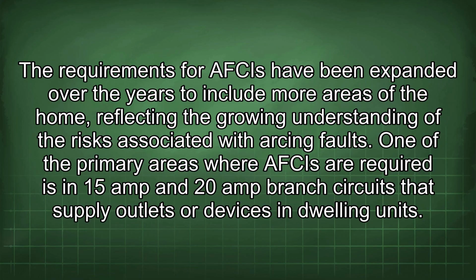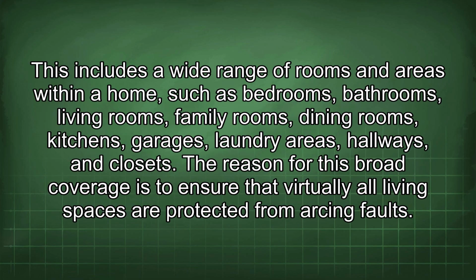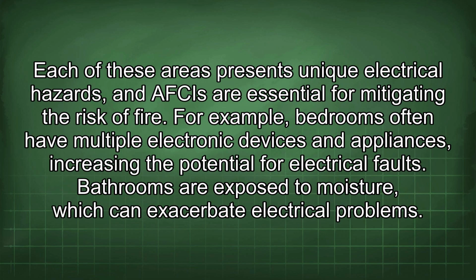One of the primary areas where AFCIs are required is in 15 amp and 20 amp branch circuits that supply outlets or devices in dwelling units. This includes a wide range of rooms and areas within a home, such as bedrooms, bathrooms, living rooms, family rooms, dining rooms, kitchens, garages, laundry areas, hallways, and closets. The reason for this broad coverage is to ensure that virtually all living spaces are protected from arcing faults. Each of these areas presents unique electrical hazards, and AFCIs are essential for mitigating the risk of fire.